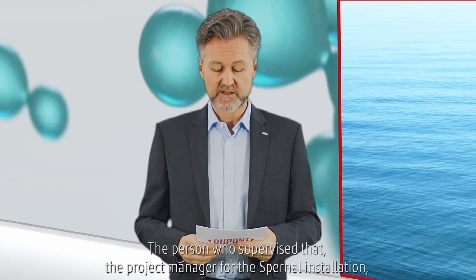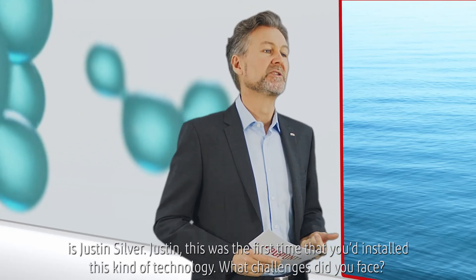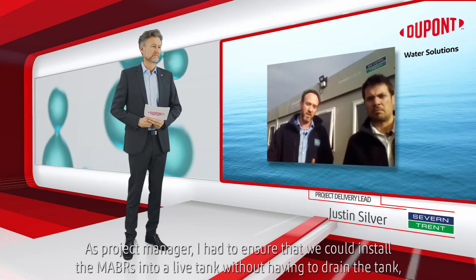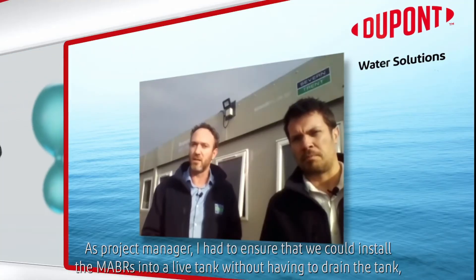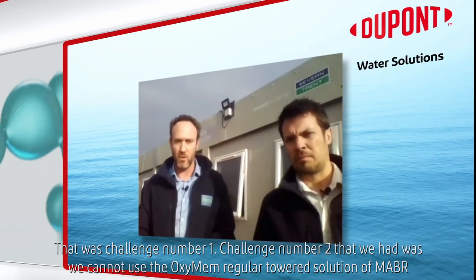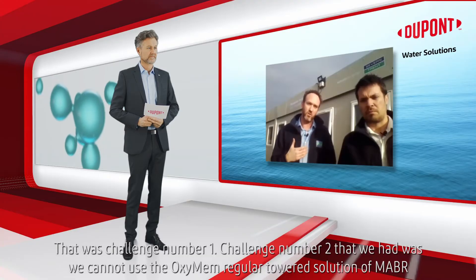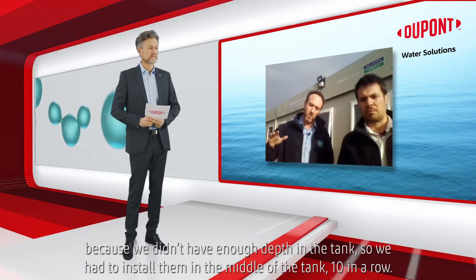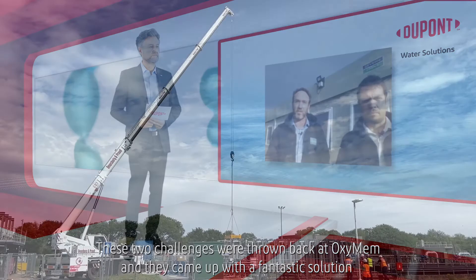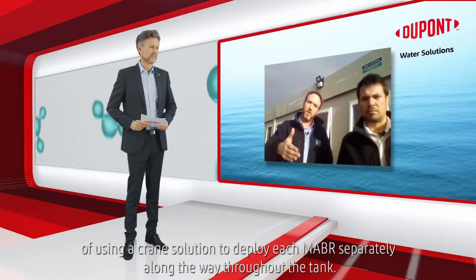The project manager for the Spernal installation is Justin Silver. This was the first time installing this kind of technology. As project manager, I had to ensure that we could install the MABRs into a live tank without having to drain the tank — the challenge was how to install 10 modules into the anoxic zone at Spernal. Challenge number two was that we couldn't use the OxyMem regular tower solution of MABR because we didn't have enough depth in the tank, so we had to install them in the middle of the tank, 10 in a row. These two challenges were thrown back at OxyMem and they came up with a fantastic solution of using a crane to deploy each MABR separately along the way throughout the tank.